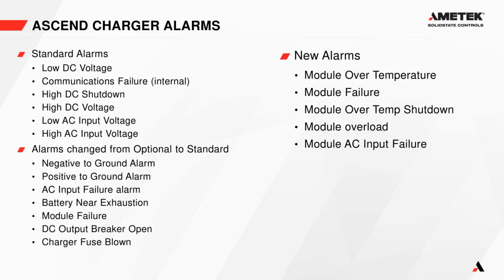And then new alarms for the Ascend 3-phase are module over temperature. When the temperature of one of the modules gets too hot, it will get this alarm. It'll indicate that either there's some kind of component failure inside your system, or that one of the fans is obstructed or failed. The module failure alarm occurs when we command a module to go to a certain voltage or power on, and it doesn't happen. You'll also get the module failure alarm when you lose communication with that module. The module over temperature alarm is like a warning that just notifies the customer that the system is in an over temperature state. If the temperature gets too high, we will shut down the module automatically to prevent damaging the module or starting a fire or something like that.